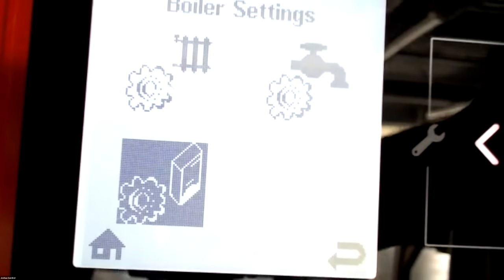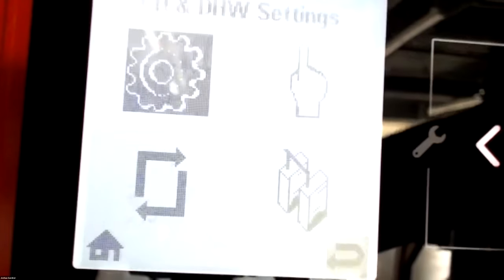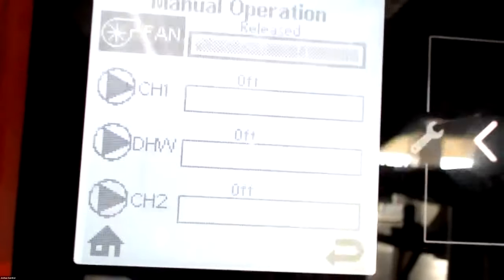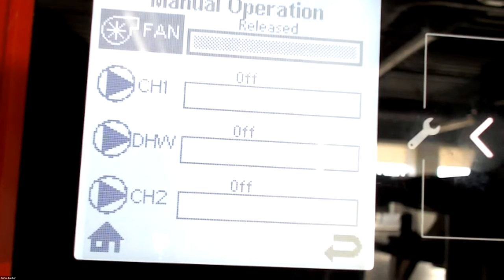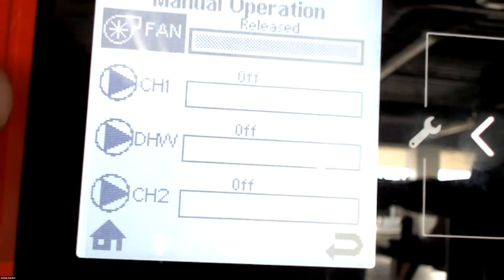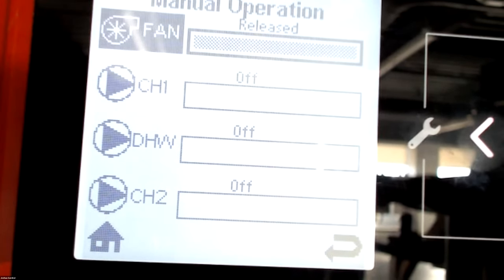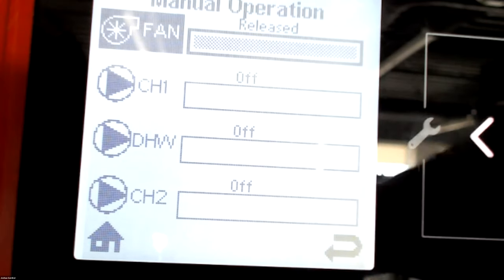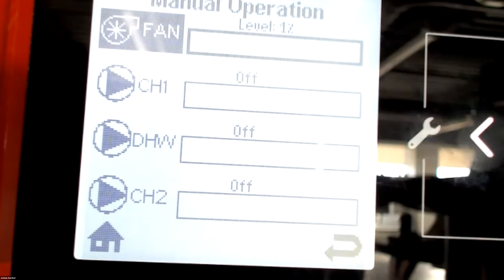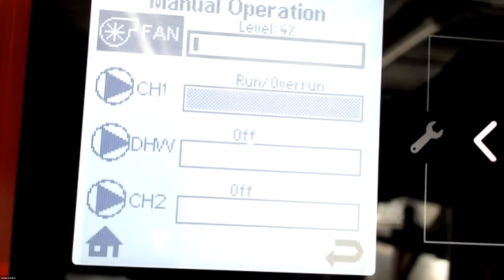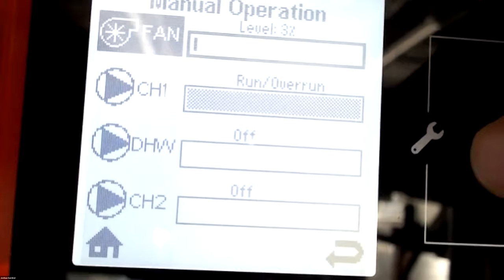Then go back one. And the manual operation. So this is where we can go in and we can manually turn pumps on and off, the fan, which this is where we are doing our setup. So when we go to commission the boiler, we're going to go into this manual operation and we're going to click the center OK button on the fan. So where it says released, that means control of the fan is released to the boiler. As soon as you hit the center OK button, it gives you level 1%. 1% is the low firing rate. You just move over and bring it up to 100%. And it'll bring in the high fire rate.